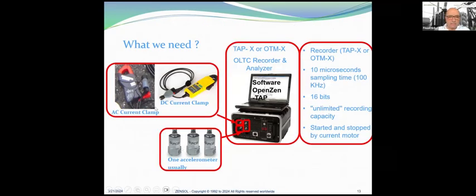What we need is an AC clamp or a DC clamp, 3 accelerometers, but usually we use only 1. Of course, the recording system with the software on the computer, and these are the specifications. As I told you, 10 microseconds. The 16-bit is important. And of course, the computer and the recording system give us unlimited recording capacity.